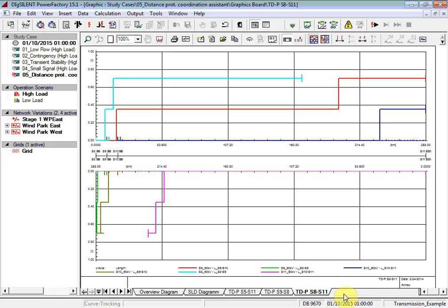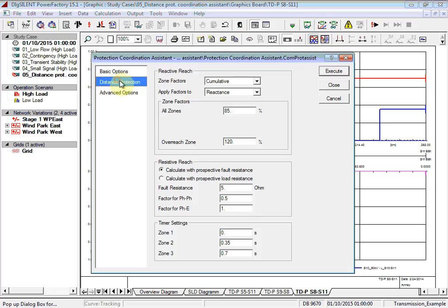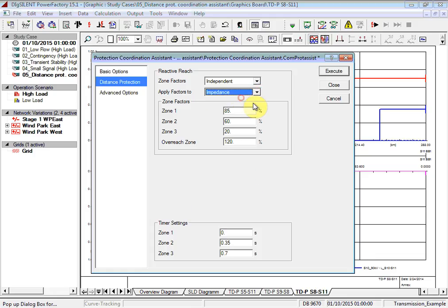In this case, the cumulative method is not necessarily the best method to use to calculate the settings. Let's try a different method. Choose the Protection Coordination Assistant button again, and let's choose the independent method. Apply the factors this time to the impedance. Use the default settings, 85%, 60% and 20%, and an overreach zone setting of 120%. Use the same time settings again.